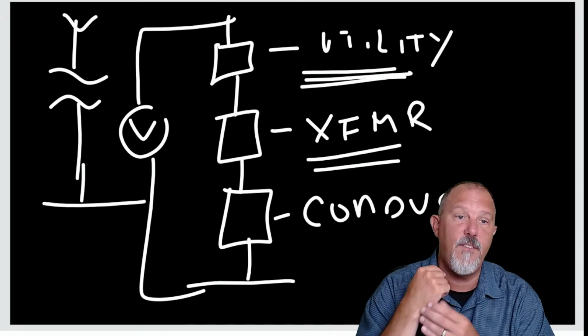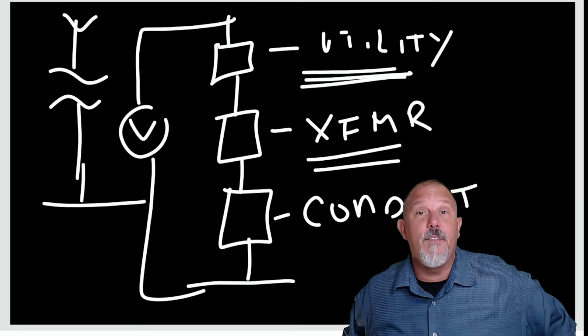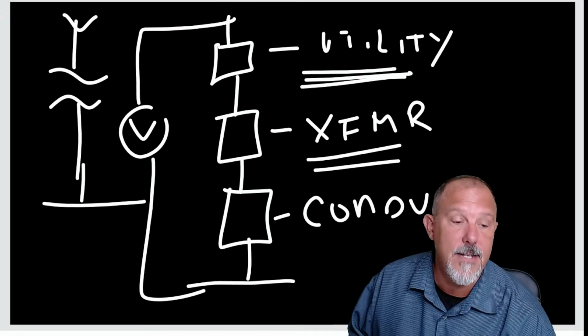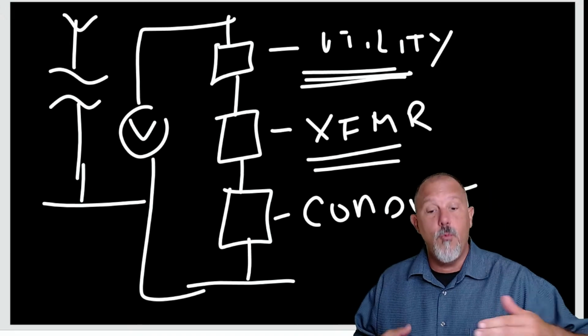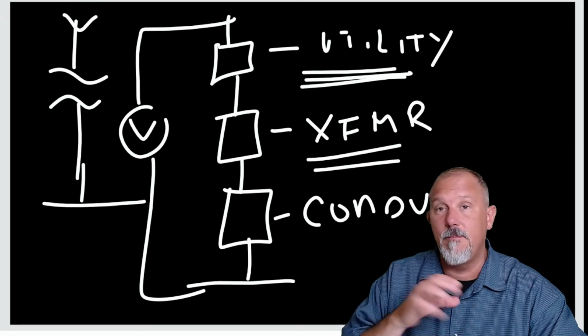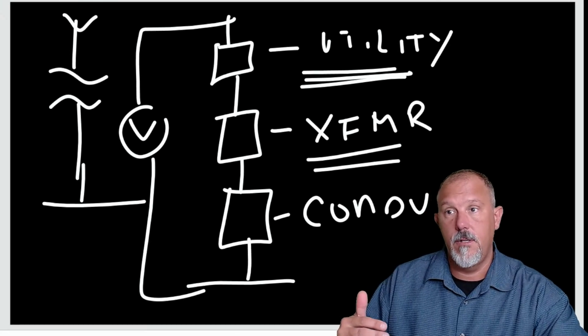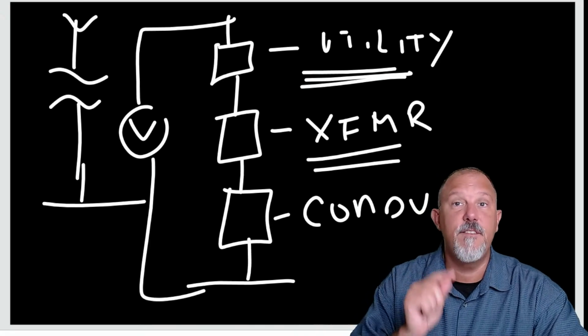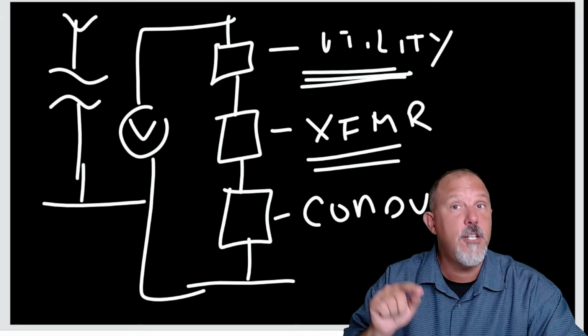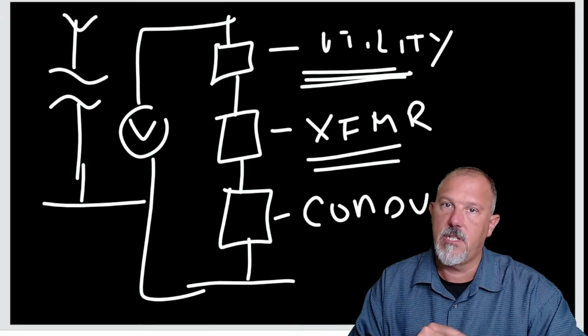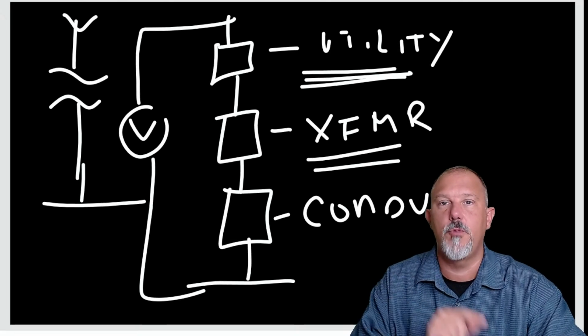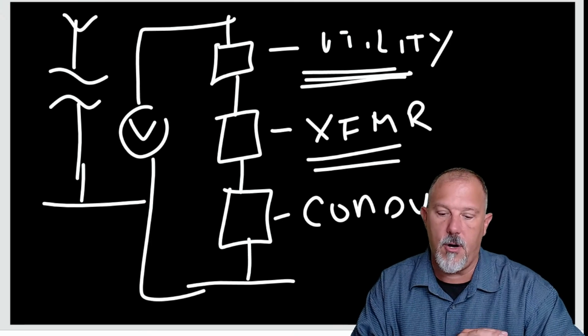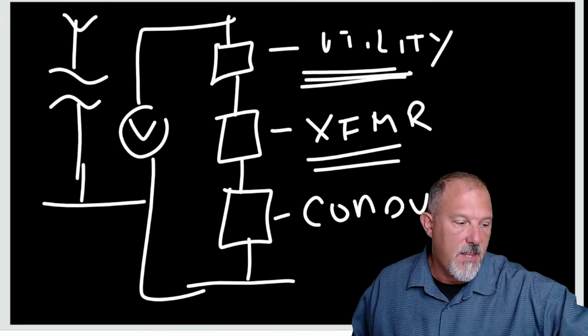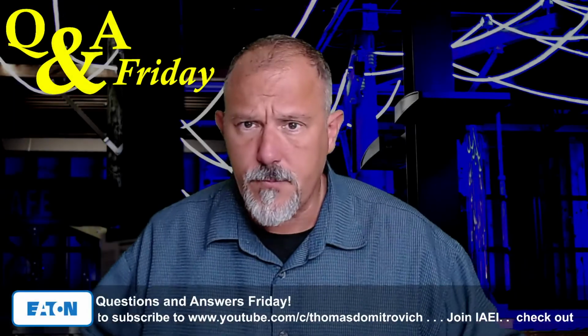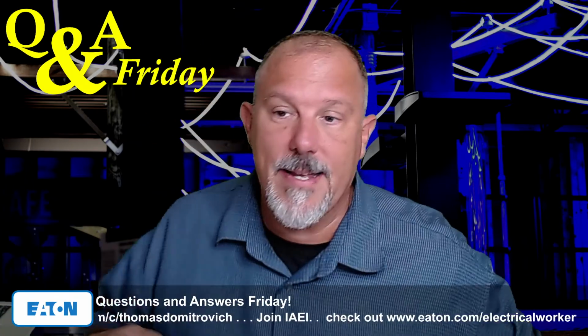And I have a video where I go through the calculations of infinite bus, and I draw this. And in fact, I did a session on per unit calculating fault currents, and we went through all the math associated with calculating fault currents. My thought process is, if you understand how to calculate short circuit currents, how to convert every component that you need to convert into an impedance within a power system, you will understand where your fault contributions come from and why the numbers are the way they are, right? So watch those two videos. I think you might get some value out of those. I'm going to leave this live over here so I can go back and get it later if I need it.